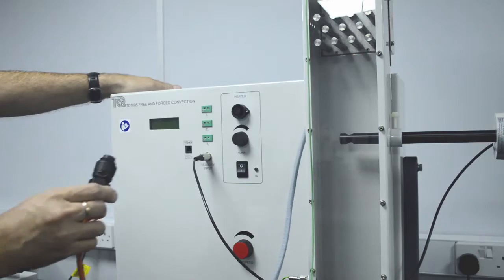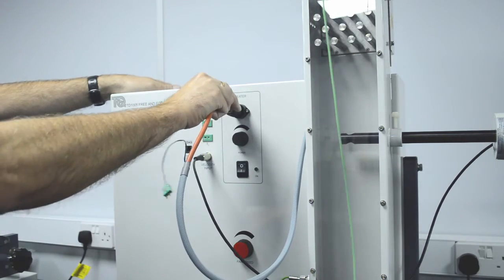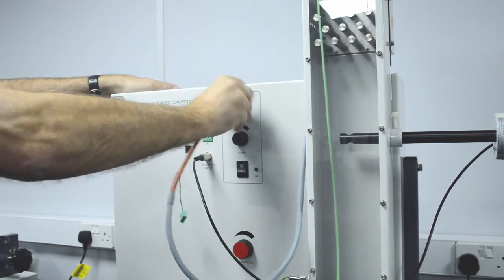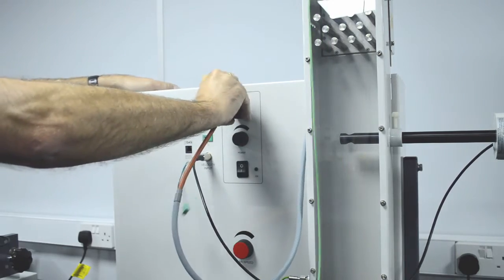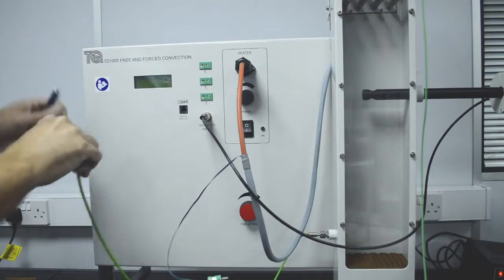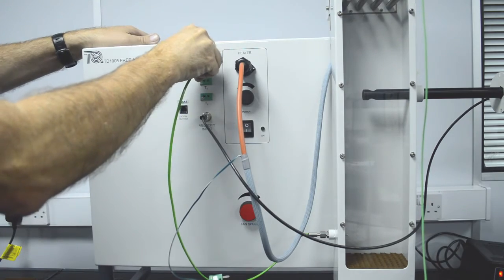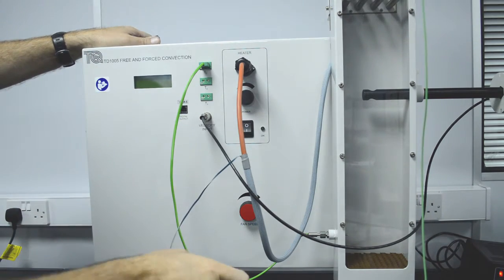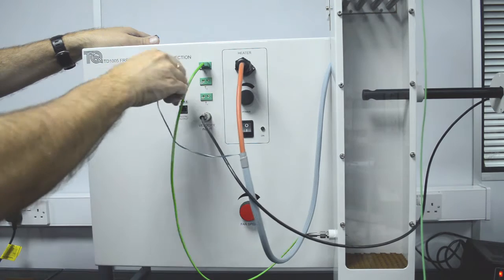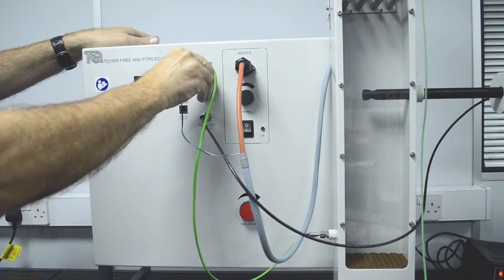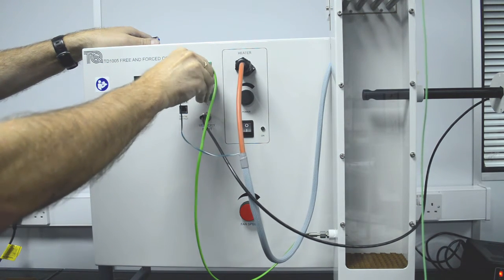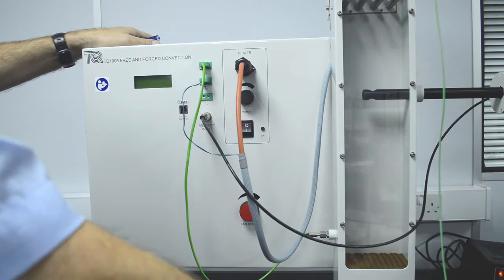Connect the heater and thermocouple cables from the heat transfer surface to the sockets on the front panel of the control unit. Connect the inlet temperature probe, the heater surface temperature probe, or the traverse temperature probe to the front panel of the control unit.